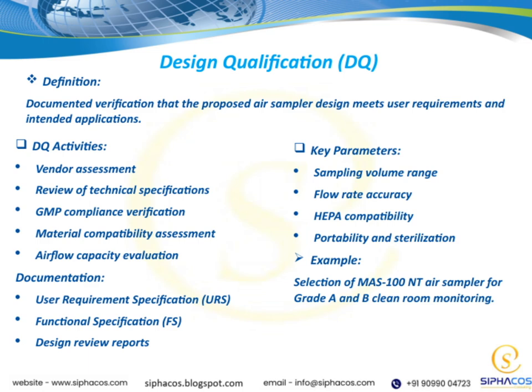All these activities are documented systematically. We prepare a user requirement specification, which captures what we need from the device, and a functional specification that details how it should perform. Additionally, we compile design review reports to record the evaluation process, ensuring everything aligns with our quality and compliance standards.